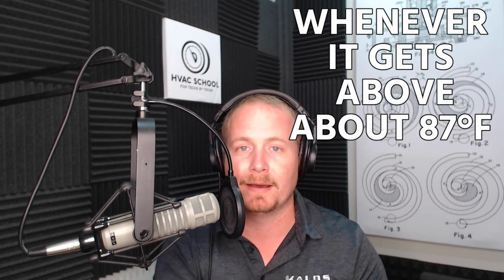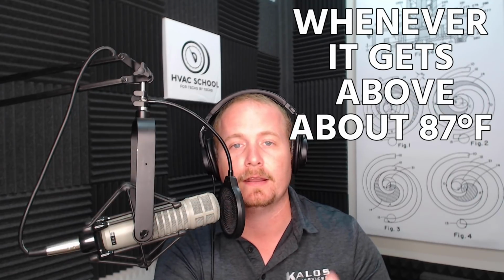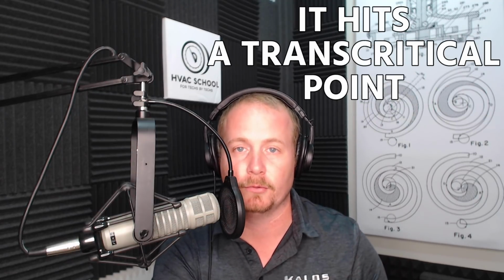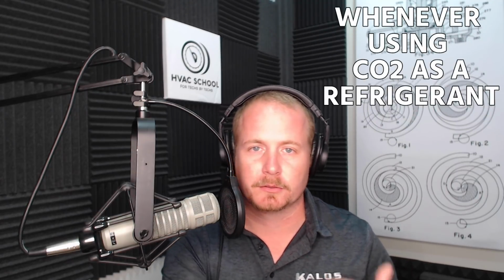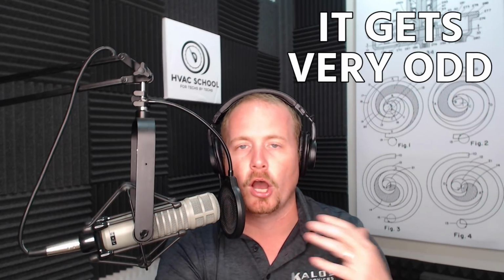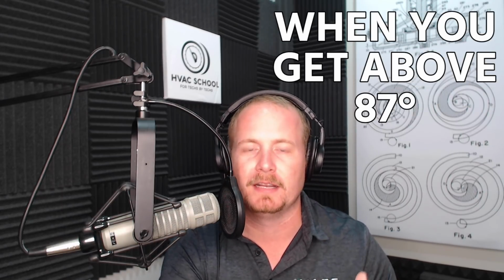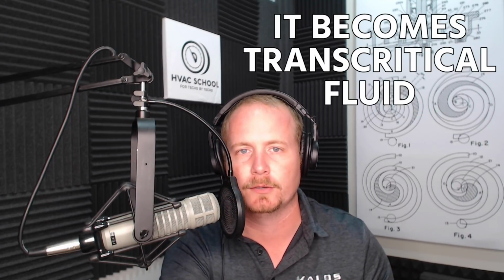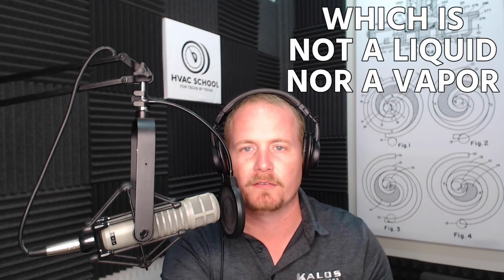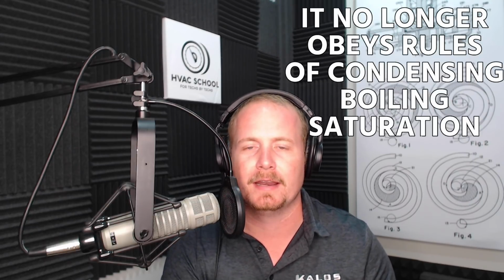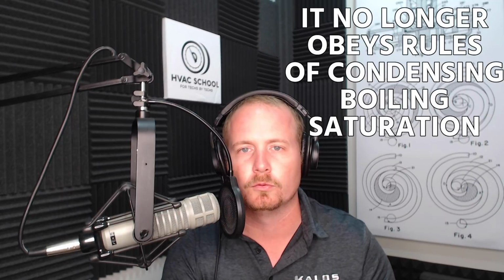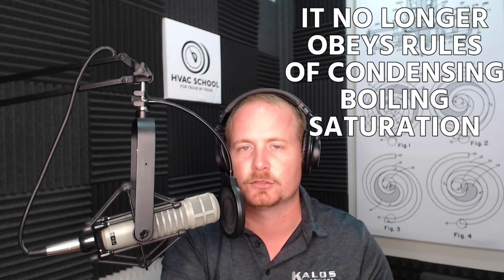So we have to have it under high enough pressure in order to keep it from hitting that triple point at the bottom. And then whenever CO2 gets above about 87 degrees Fahrenheit, that's where it hits the transcritical point. Whenever we were using CO2 as a refrigerant, it gets very odd by our standards when you get above 87 degrees because it doesn't change into a liquid the way we're used to in condensing. It becomes what's called a transcritical fluid, which is really neither a liquid or a vapor. It's kind of its own thing, and it no longer obeys those sort of rules of condensing and boiling or saturation that we're used to.